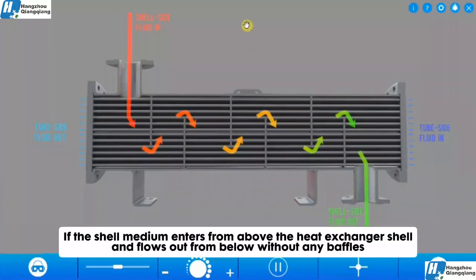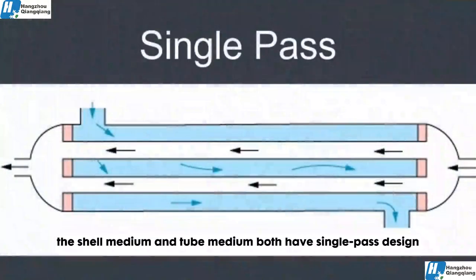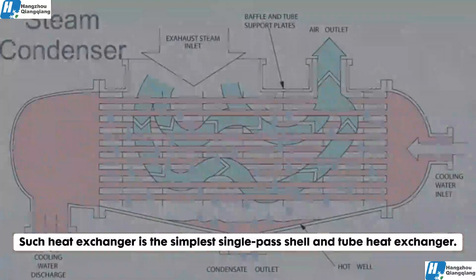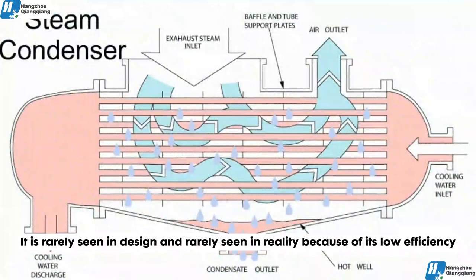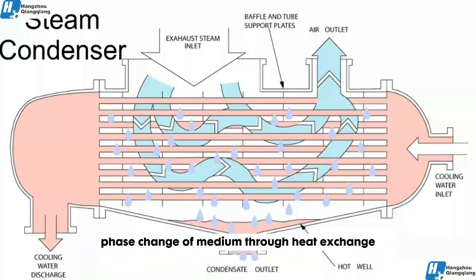If the shell medium enters from above the heat exchanger shell and flows out from below without any baffles, the shell medium and tube medium both have a single-pass design. Such a heat exchanger is the simplest single-pass shell and tube heat exchanger. It is rarely seen in design and rarely seen in reality because of its low efficiency. It is usually used when steam needs to be condensed into water or when you want to achieve phase change of a medium through heat exchange.